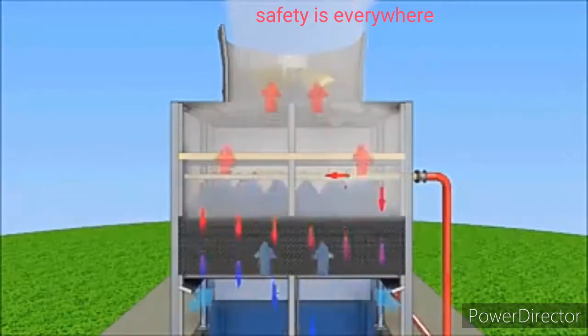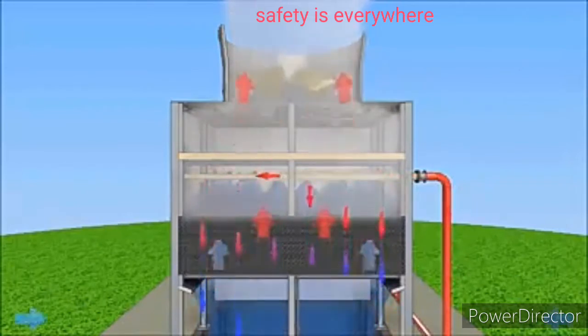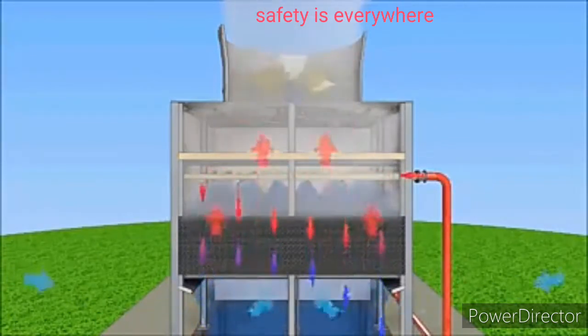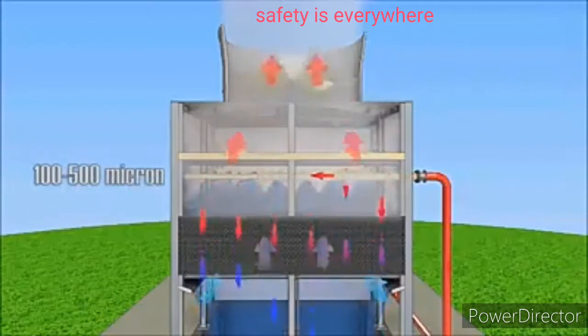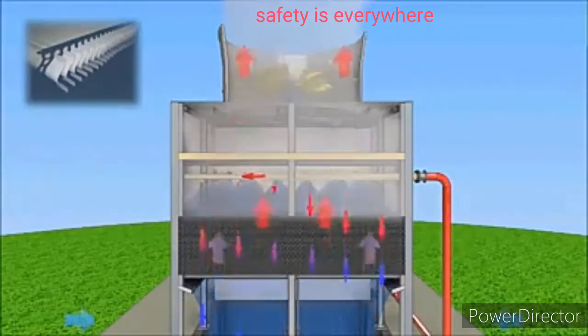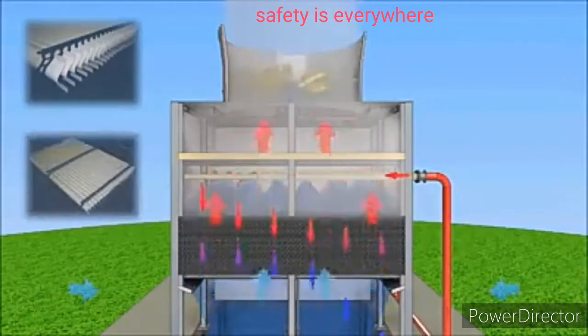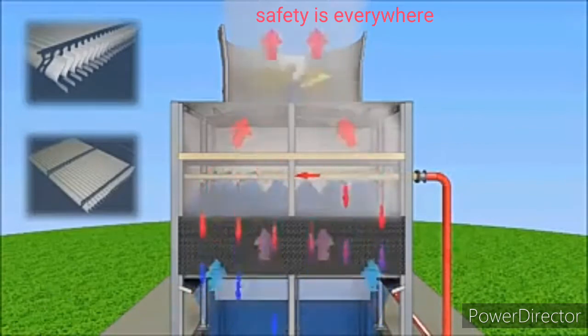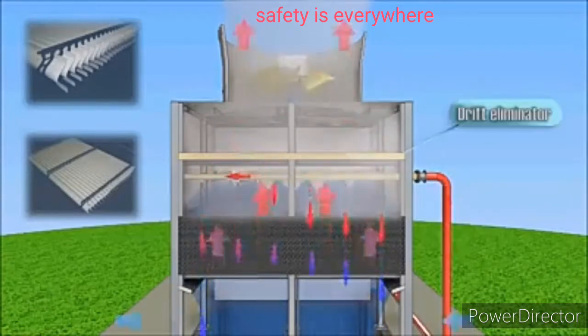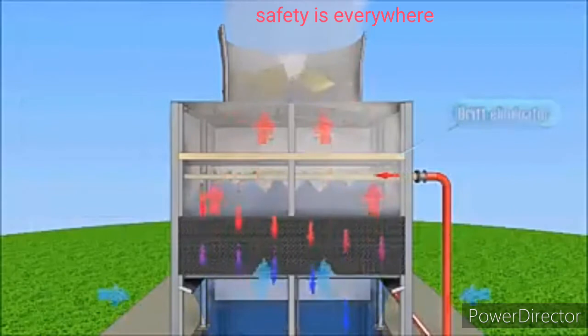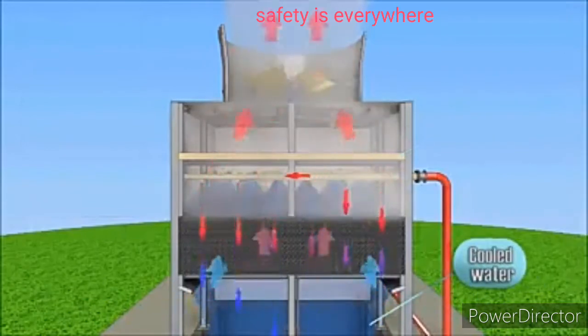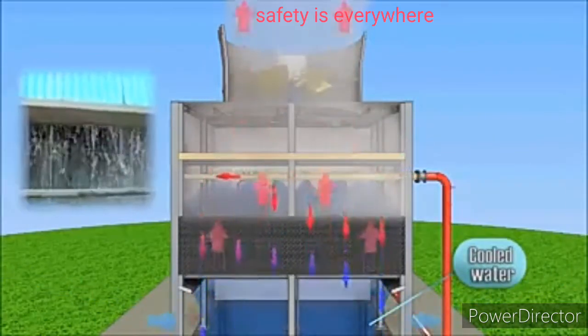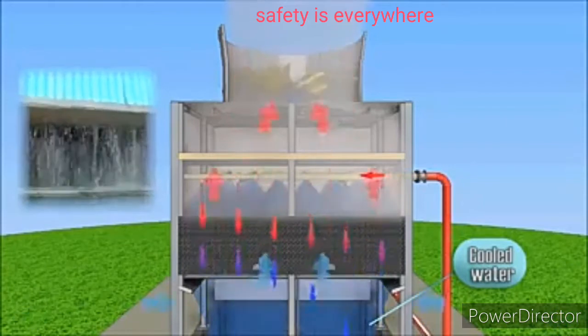An operating cooling tower emits air saturated with water vapor and containing water droplets with a size of 100-500 microns. To prevent entrainment of water droplets, a drift eliminator is installed above the water distribution system. Cooling water moves down and flows into a catchment tank, and then is supplied by the pump to the technology.